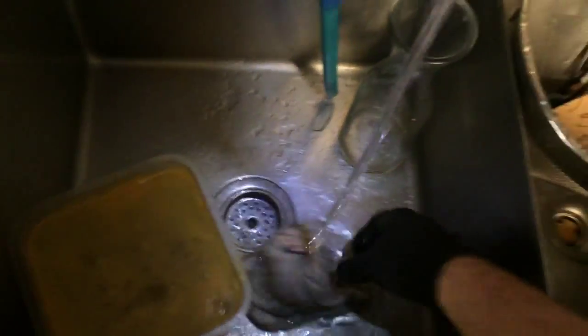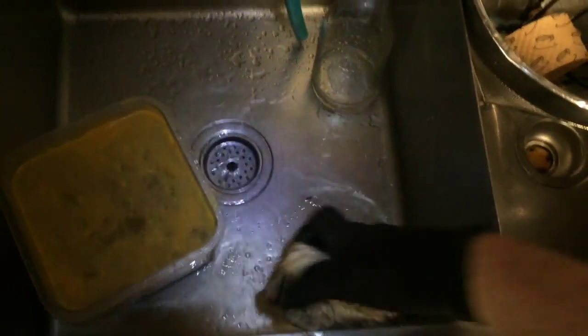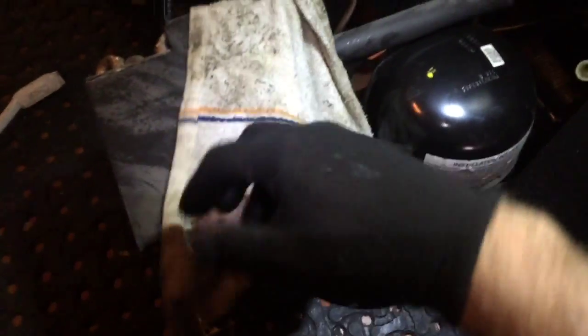With your nitro setup, I'll show you a nice little trick with the towel right there. If you want to go ahead and get your rag good and damp, put the rag — your little towel — right here on the back of the condenser. What that's gonna do is catch all the dust when we blow this coil out.